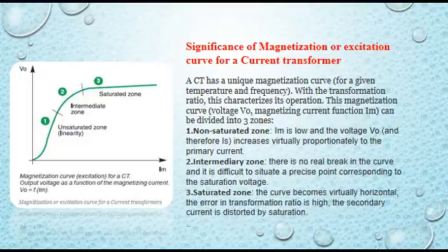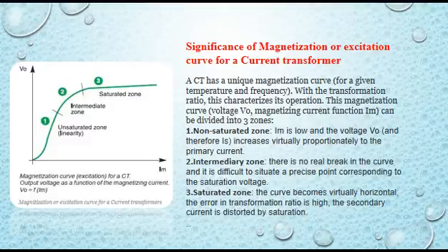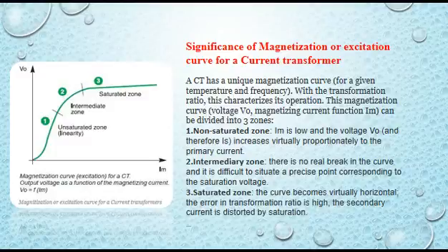The significance of the magnetization or excitation curve of a CT is that a CT has a unique magnetization curve for a given temperature and frequency and transformation ratio, which characterizes its operation. This magnetization curve — voltage versus magnetization current Im — can be divided into three zones: the non-saturated zone, the intermediary zone, and the saturated zone.